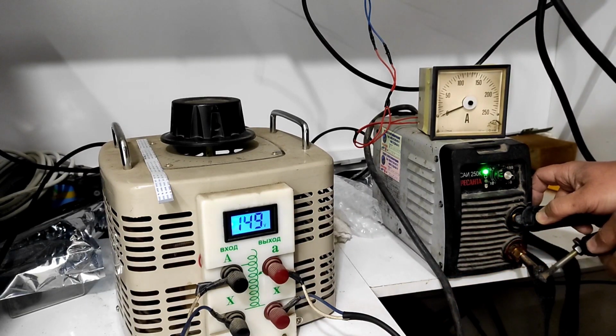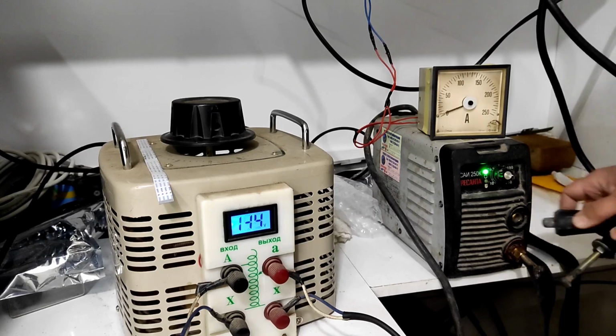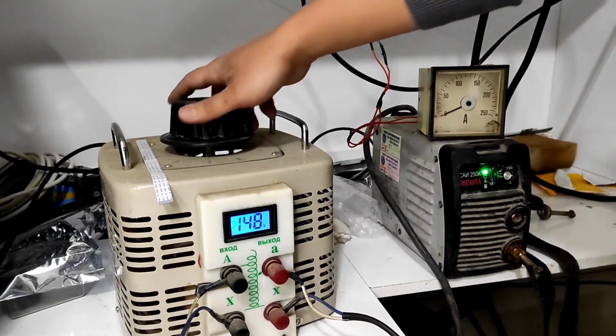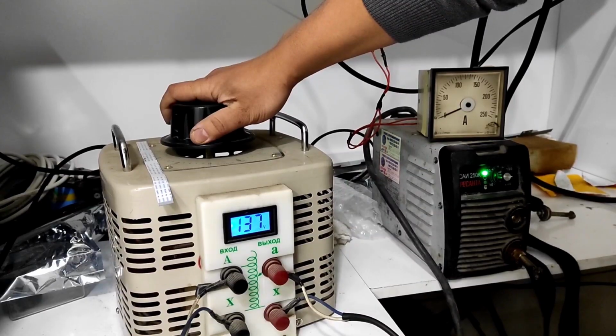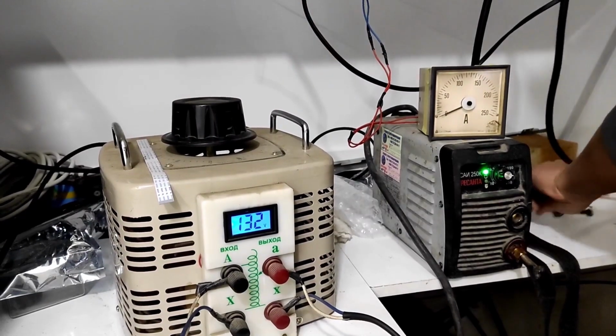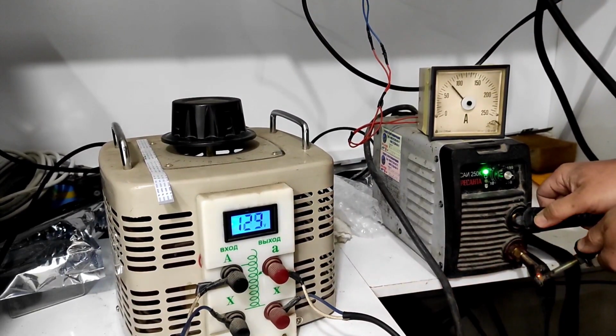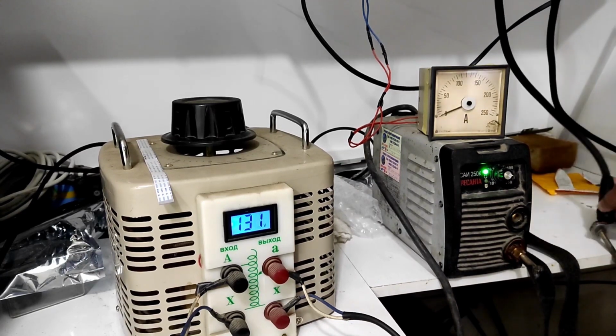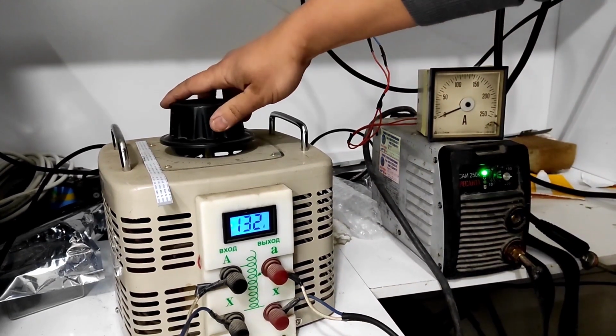Now let's test the unit under low input voltage conditions. We reduce the input voltage to 150 V. The machine continues to operate correctly and delivers 120 amps. We lower the voltage even further to 130 V. And the output current is 80 amps.